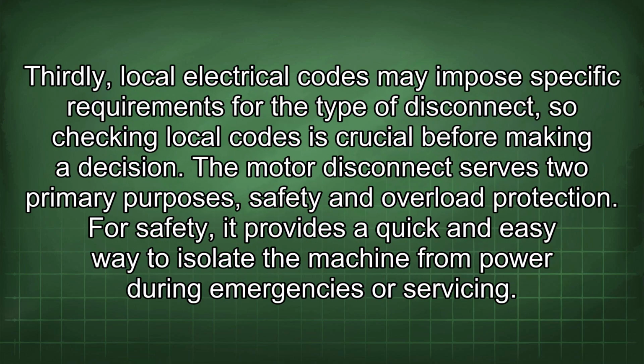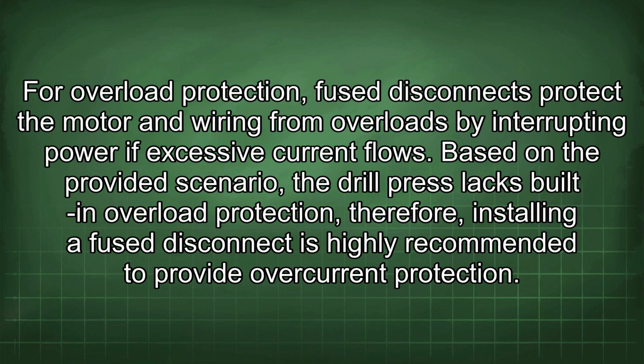Thirdly, local electrical codes may impose specific requirements for the type of disconnect, so checking local codes is crucial before making a decision. The motor disconnect serves two primary purposes: safety and overload protection. For safety, it provides a quick and easy way to isolate the machine from power during emergencies or servicing. For overload protection, fused disconnects protect the motor and wiring from overloads by interrupting power if excessive current flows.